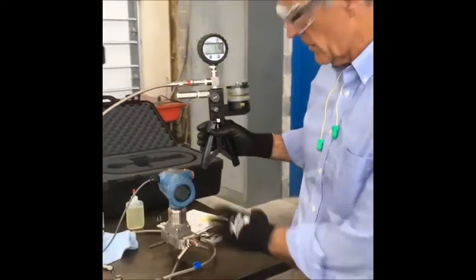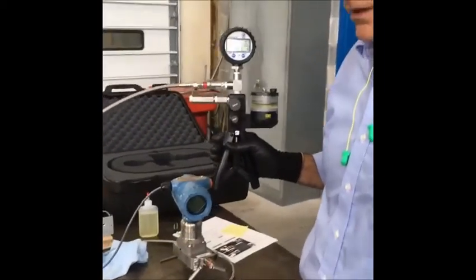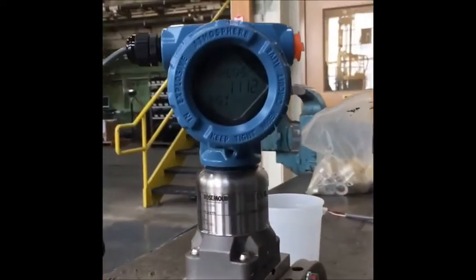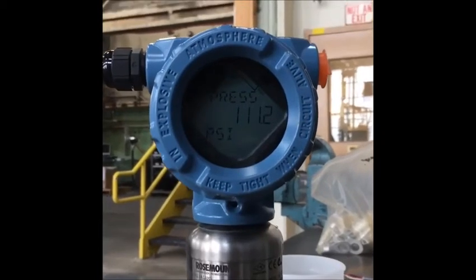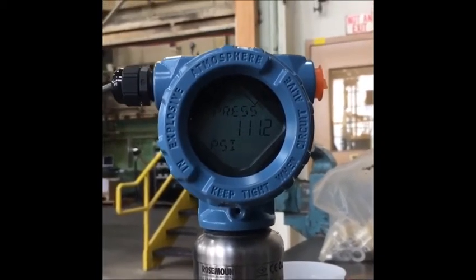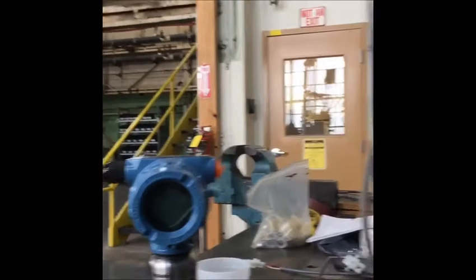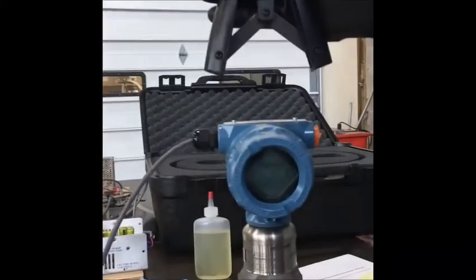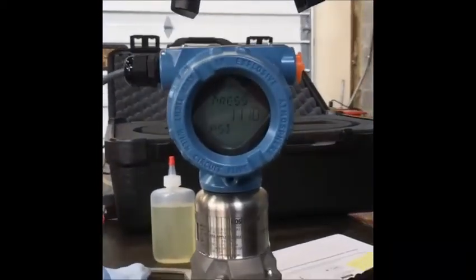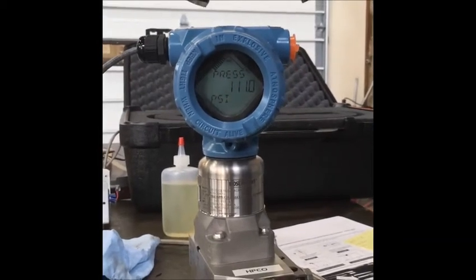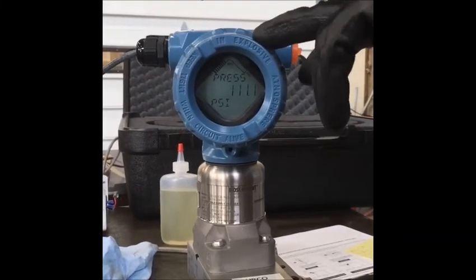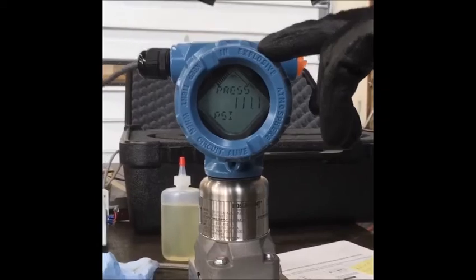Okay, we have two different pressure transducers here you can see. This one is showing discharge pressure, which we have it connected to a nitrogen bottle, but you can see it's reading about 111 PSI. That's actually A. And then we have a second transducer that's simulating our high pressure cutout, and it's reading approximately the same pressure in PSIA.